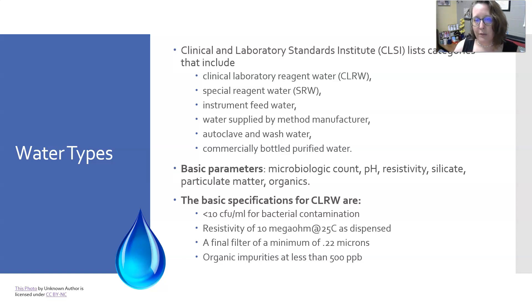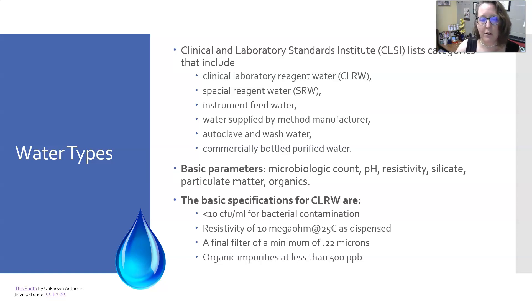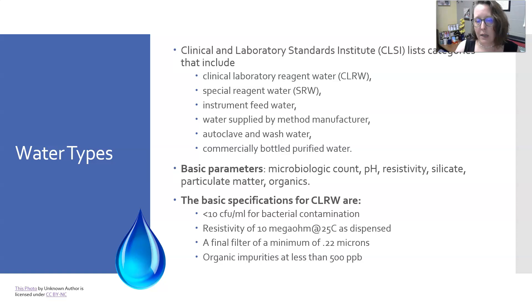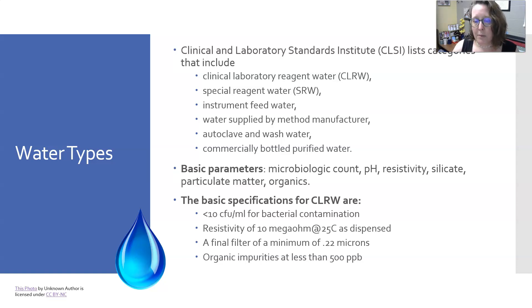The basic parameters that differentiate these types of water are microbiological counts, pH, resistivity, silicate content, particulate matter content, and organic content. The basic specs for clinical laboratory reagent water are 10 CFU or less per ml for bacterial contamination, a resistivity of 10 mega-ohms at 25 degrees Celsius as dispensed, a final filter of a minimum of 0.22 microns, and organic impurities at less than 500 parts per billion.